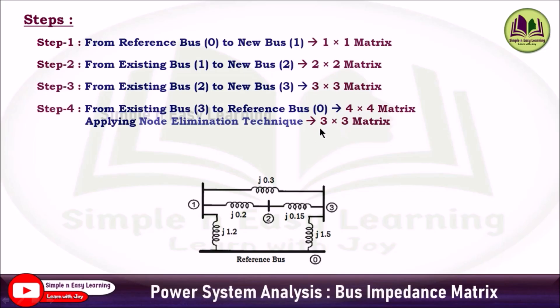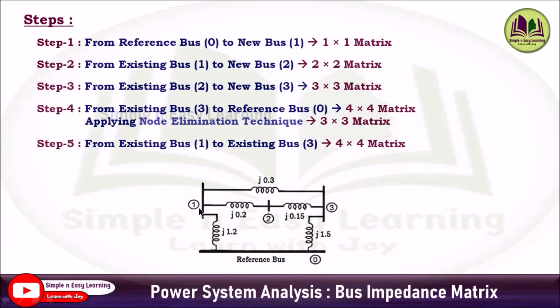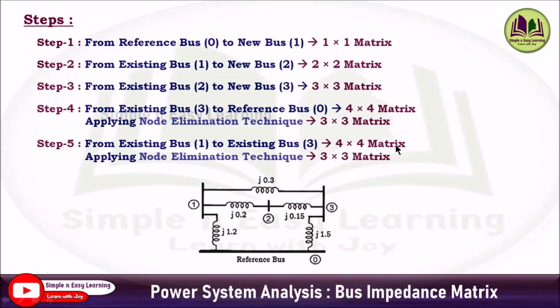One more reactance is left — j0.3 is connected between bus 1 and bus 3. In step 5 we consider that: from bus 1 to bus 3, now both buses are existing buses, so the matrix again becomes 4×4. We apply node elimination technique again to bring the final answer to 3×3. We start from the reference bus, then 1 to 2, bus 2 to 3, then 3 to reference, and finally consider j0.3.